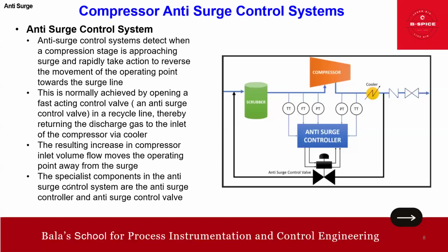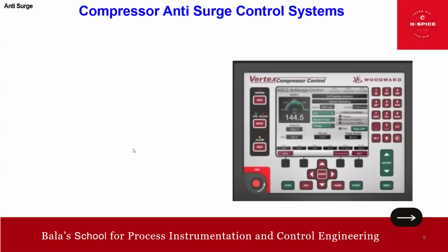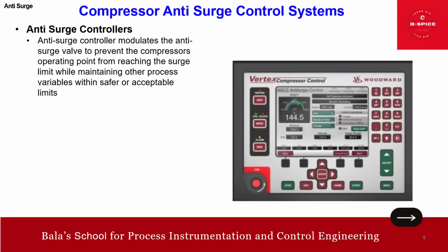So the specialist components in the anti-surge control system are, of course, the anti-surge controller and the anti-surge control valve, and additionally these transmitters, which we talked about earlier. So now we go into the anti-surge controllers. This is the look and feel of one of the Woodward controllers.